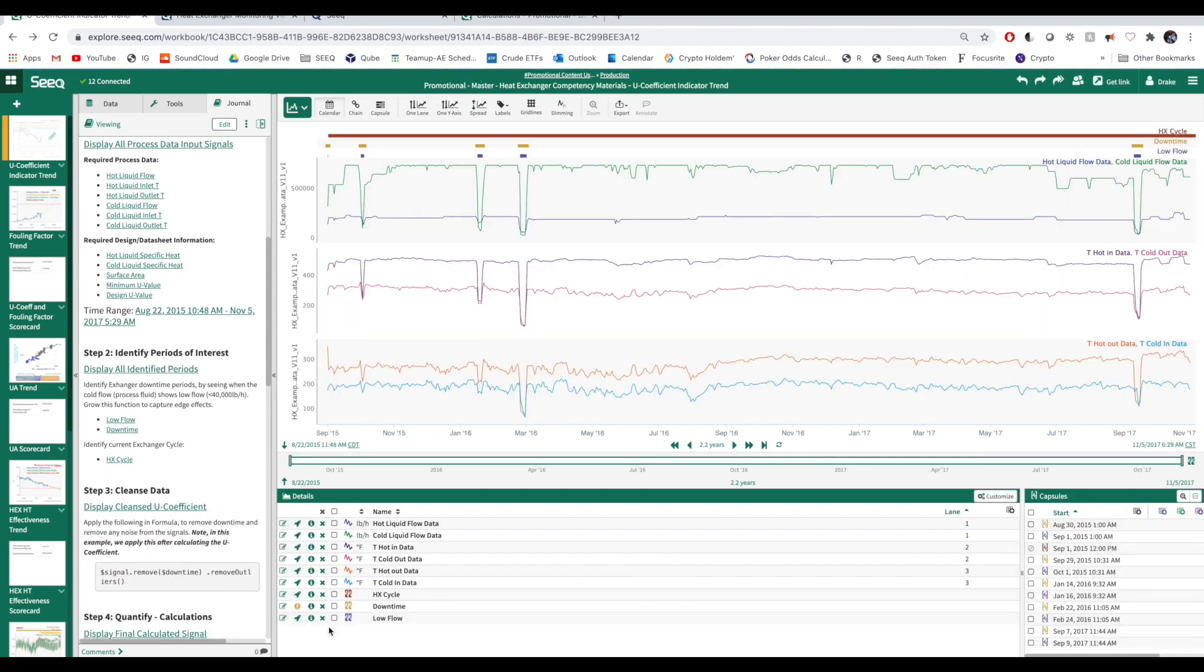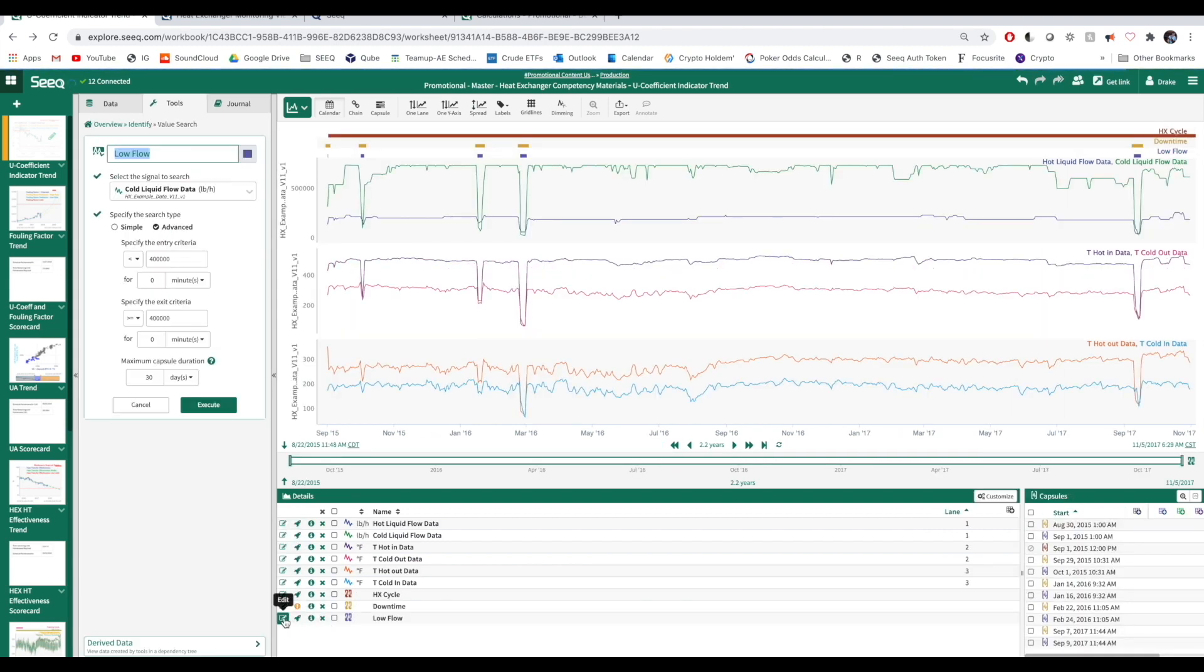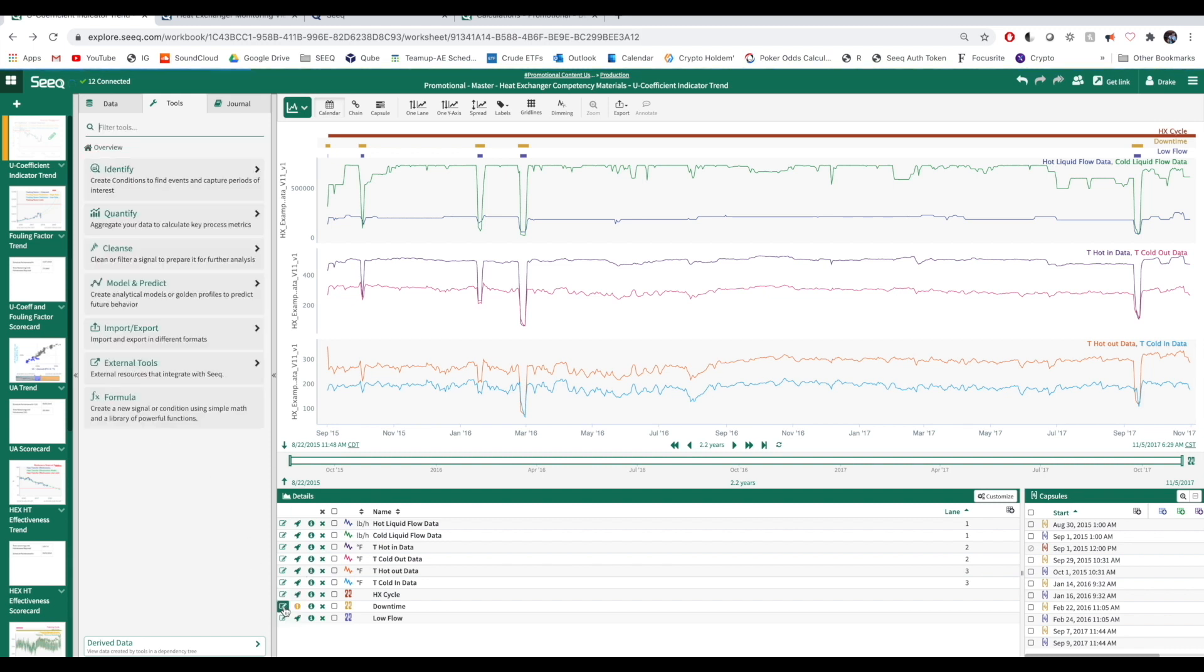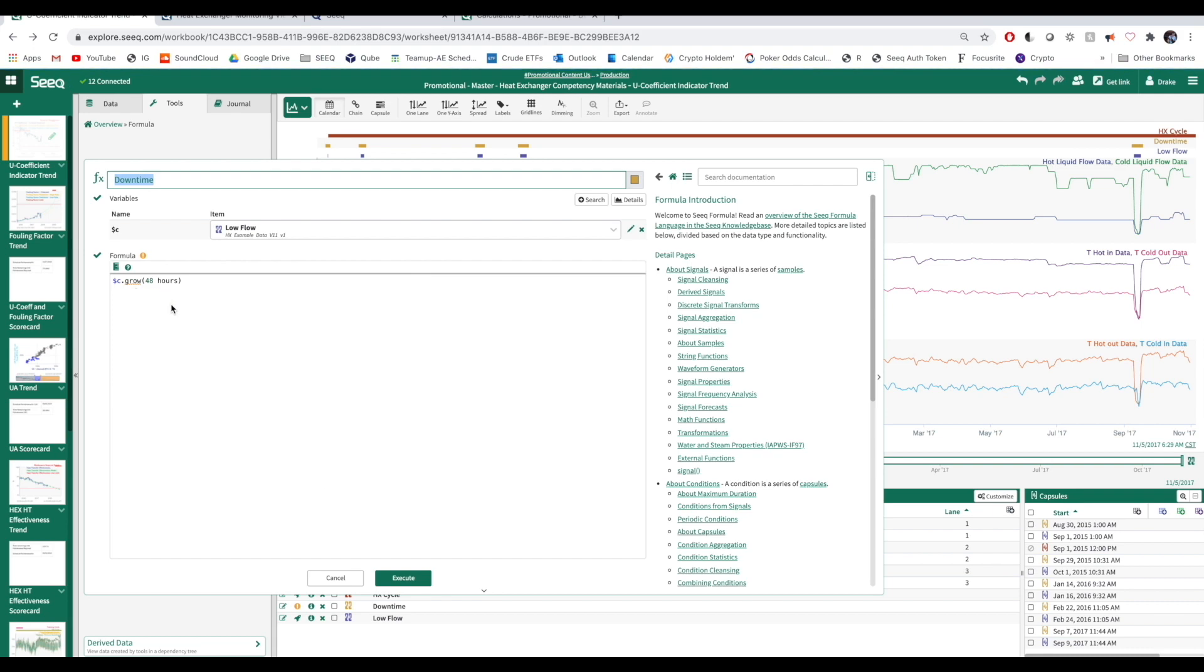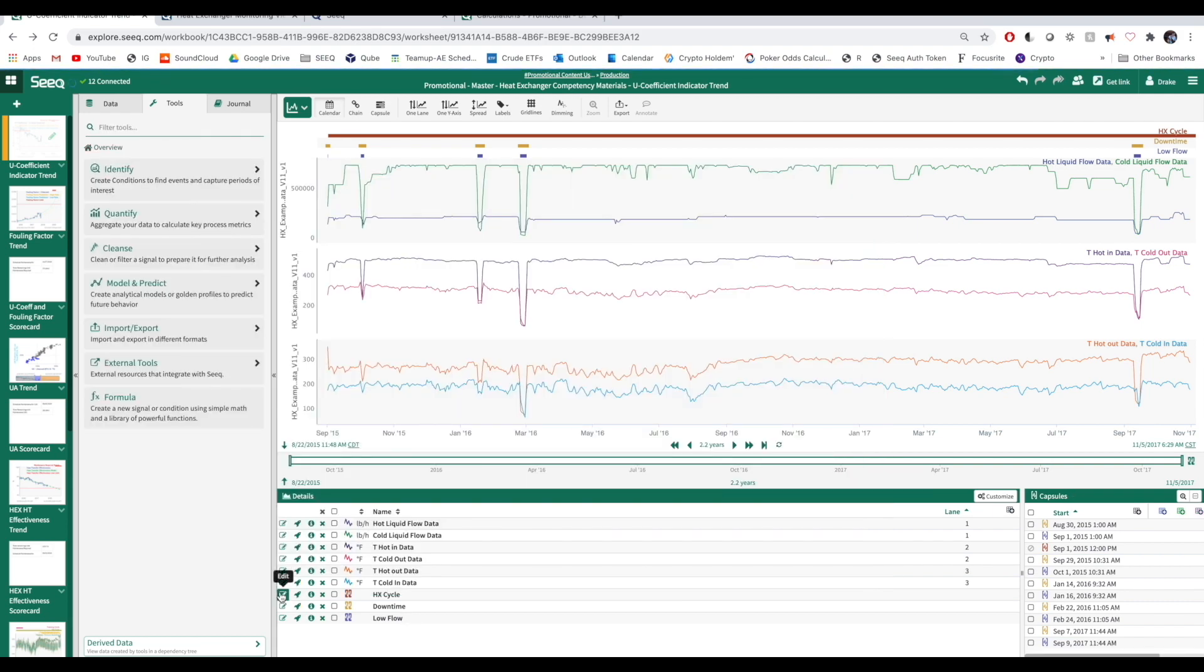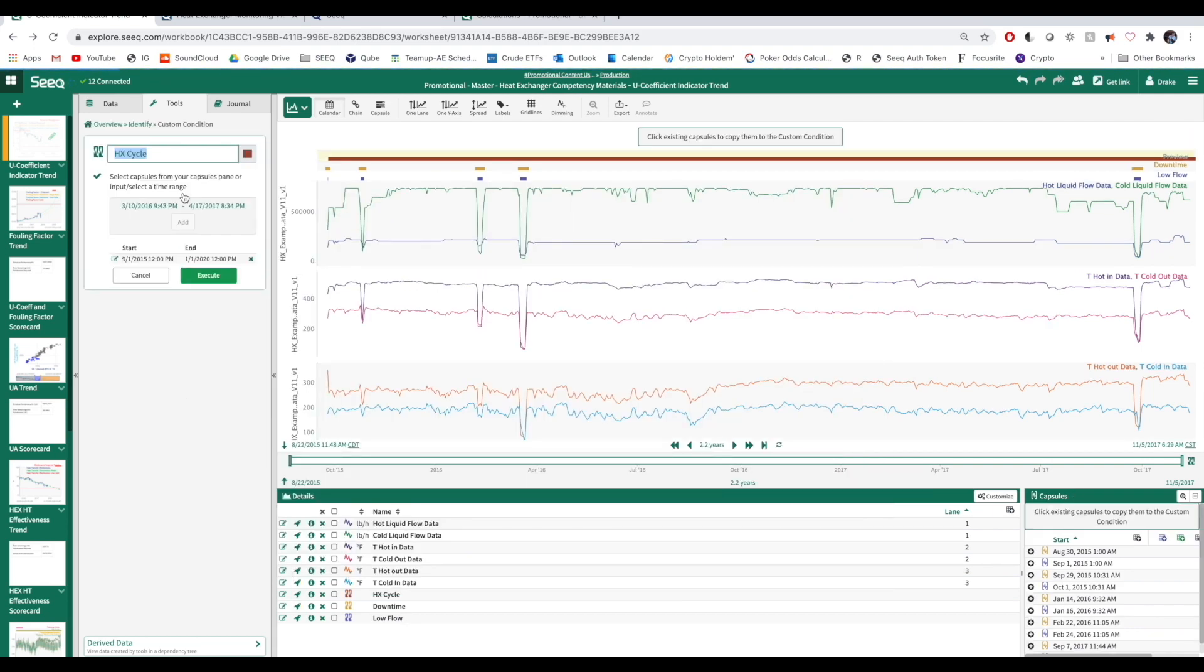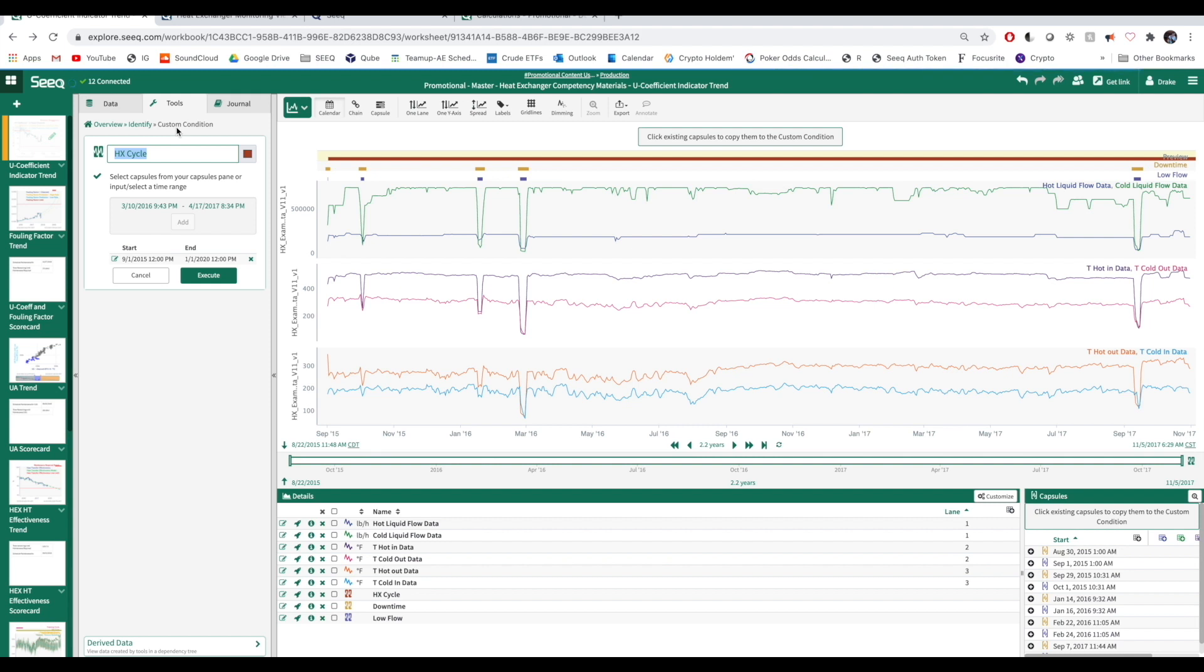Next, we need to identify periods of interest. We've identified low flow periods using value search and can extend these capsules by 48 hours using the GROW function to create a downtime condition. Now we can use custom condition to define a heat exchanger cycle.